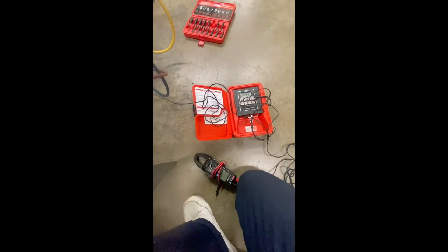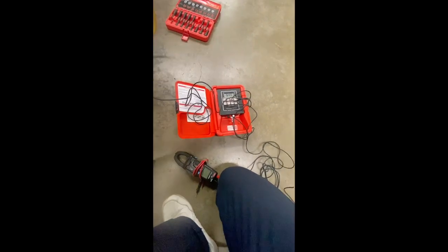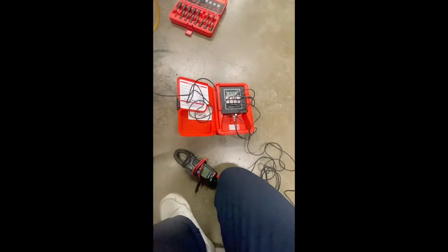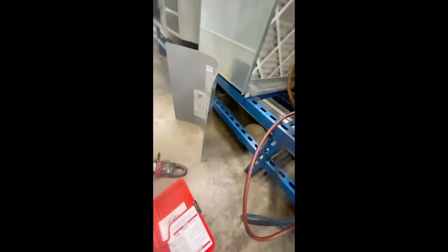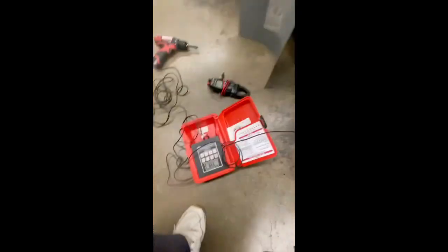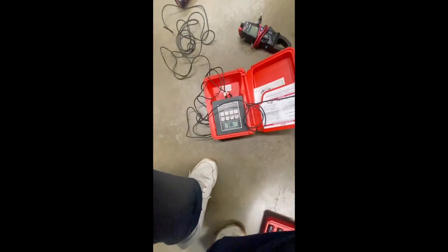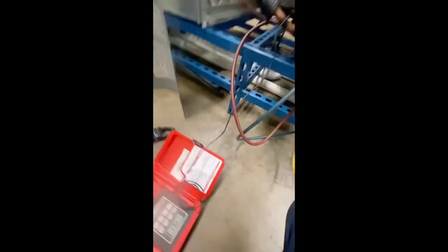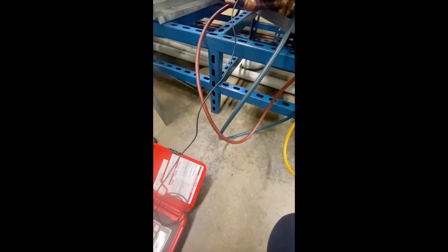I got the right probe. So what I'm doing now is I'm going to recheck those temperatures on each of those lines, the liquid line and the suction line. And then I'm going to find out my superheat and my subcooling numbers. I'm not working with a digital Fieldpiece. I'm working with analog, so I'm going to have to do all the math pretty much in my head. The digital ones are pretty cool because they have all of that math figured out for you. You don't have to do all of that.